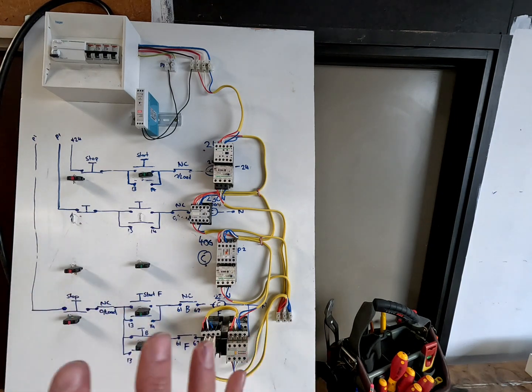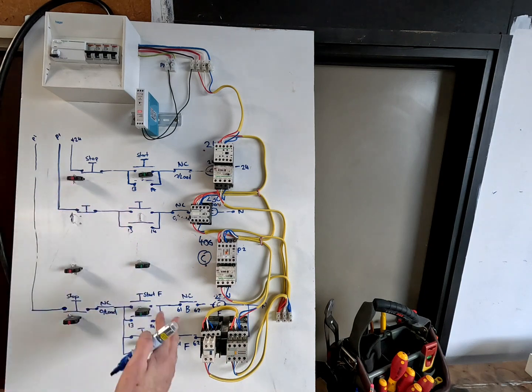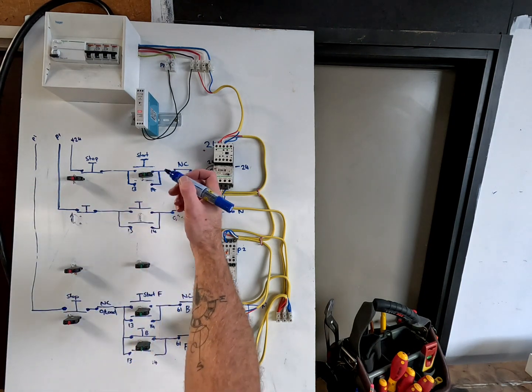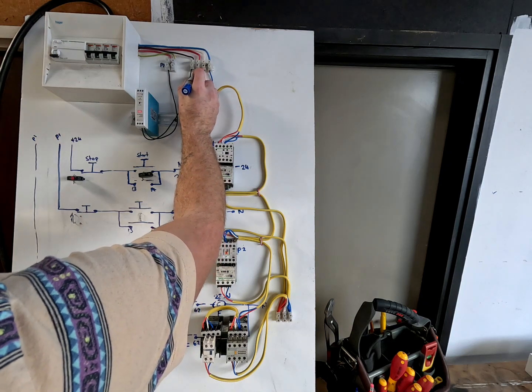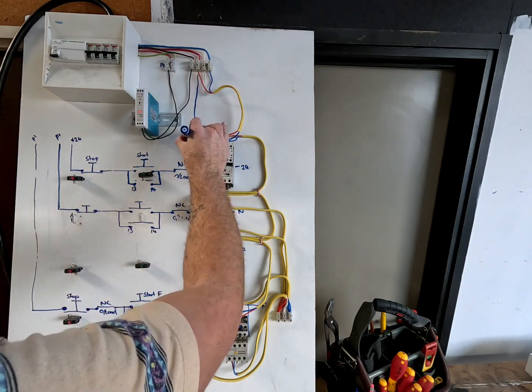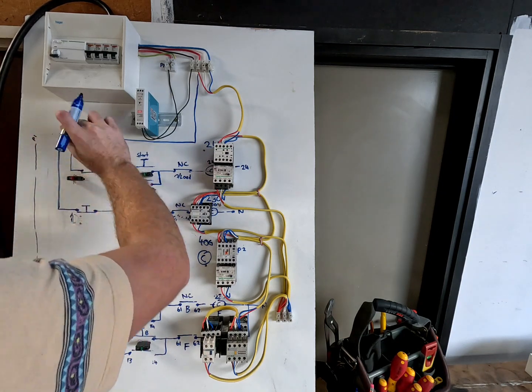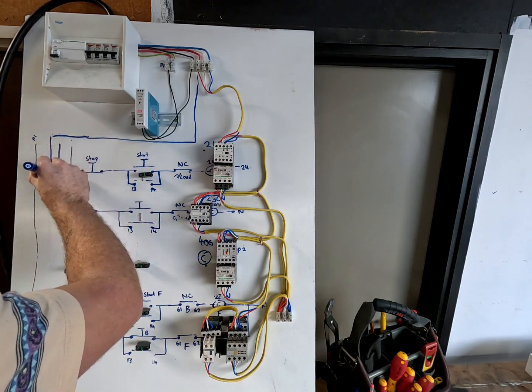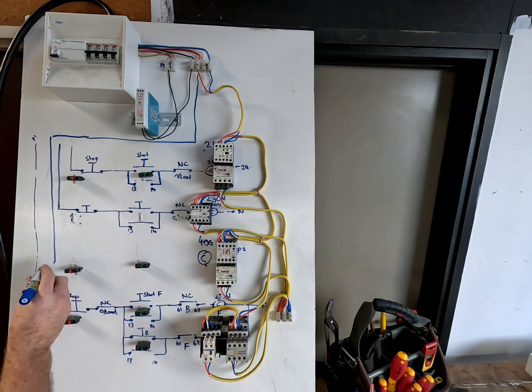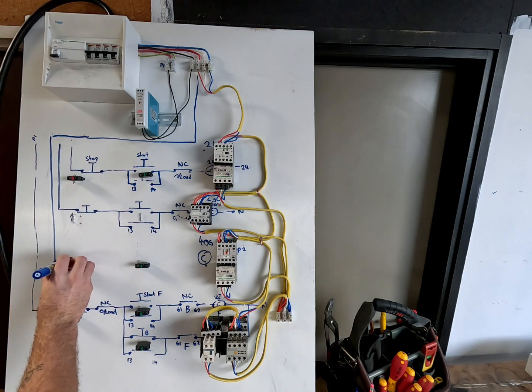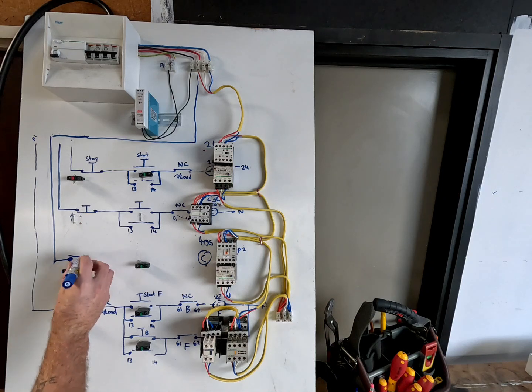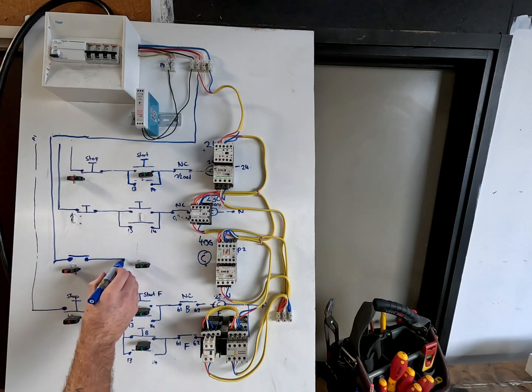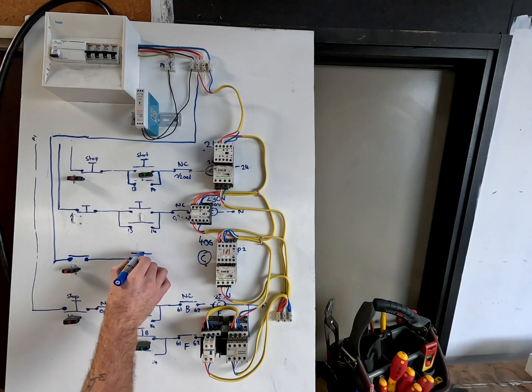Now we're going to take our phase from the first phase. You could take any phase, but we're just going to use first phase this time across here and down into our stop button. Remember, the stop is a normally closed contact. All stop buttons are. Then it comes across here to the start button, and that's an open contact.